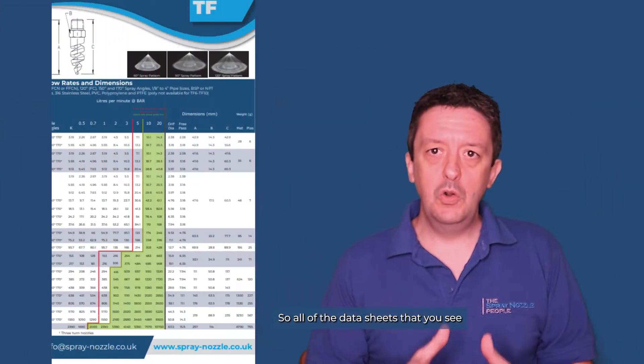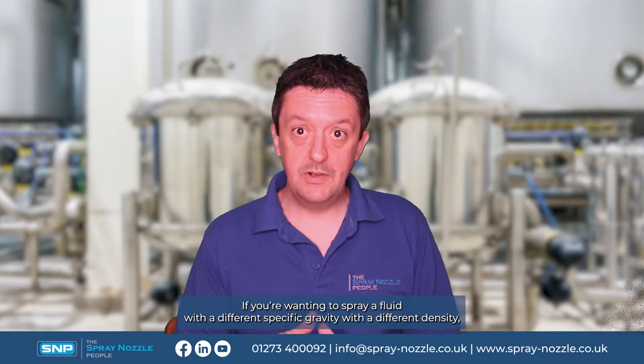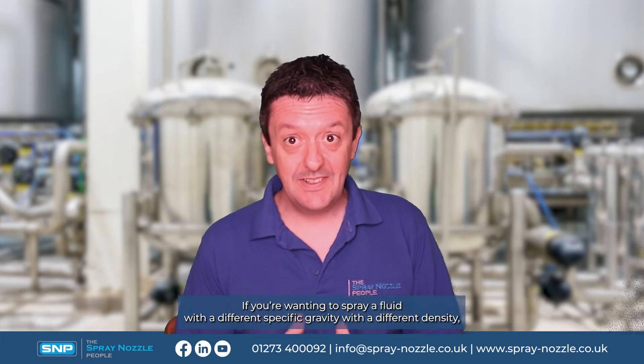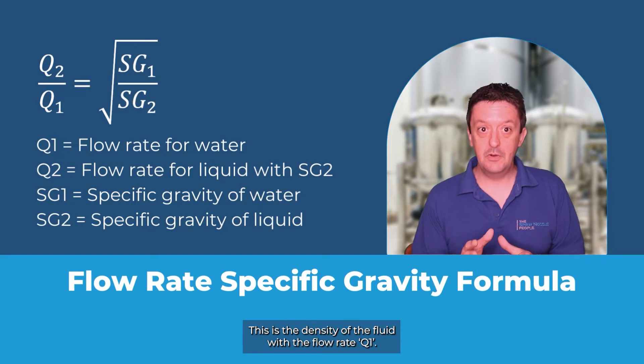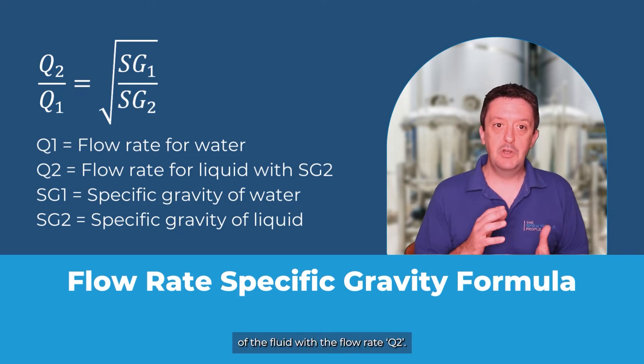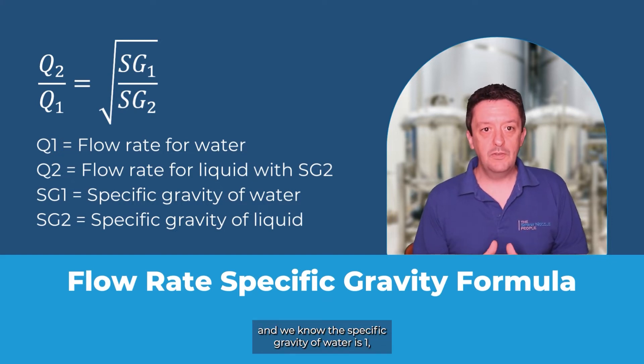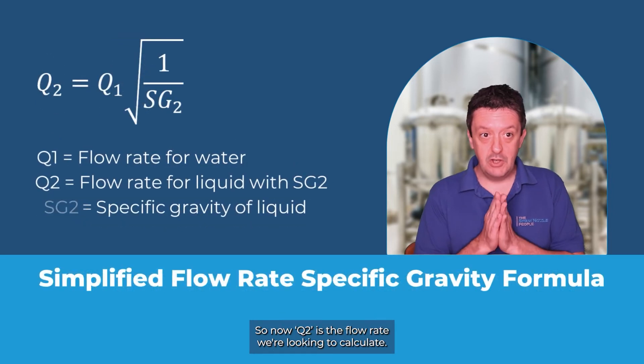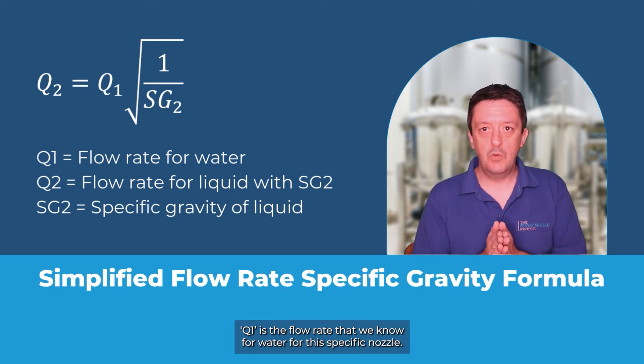The next factor that affects flow rate is the specific gravity of the fluid. All of the data sheets you'll see will have those flow rates calculated for water. If we want to spray a fluid with a different specific gravity — a different density — then we need to adjust those flow rates accordingly. This can be calculated using this formula, where SG1 is the specific gravity of the fluid with flow rate Q1, and SG2 is the specific gravity of the fluid with flow rate Q2. Since the specific gravity of water is 1, we can simplify this formula.